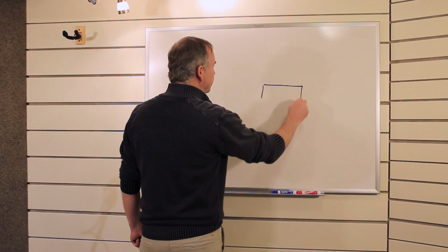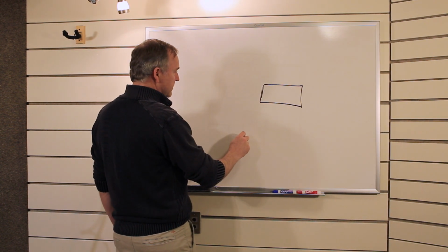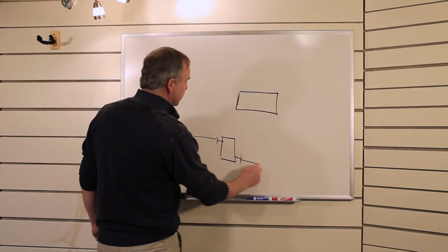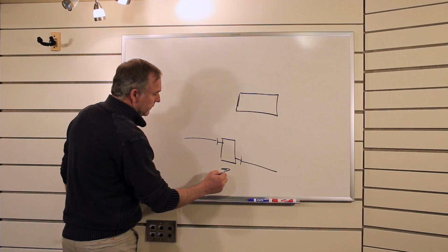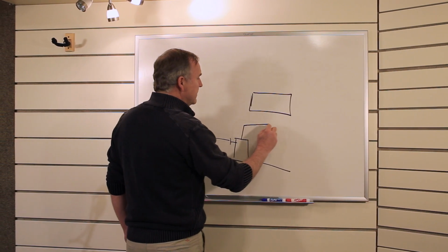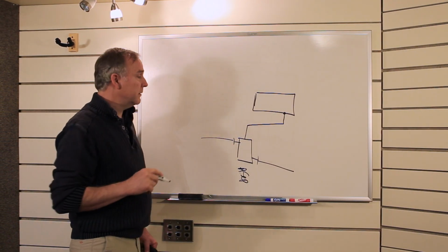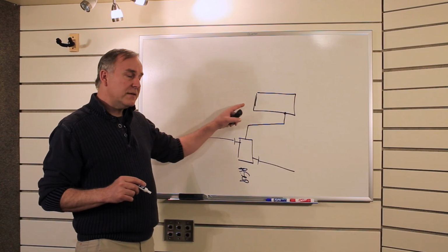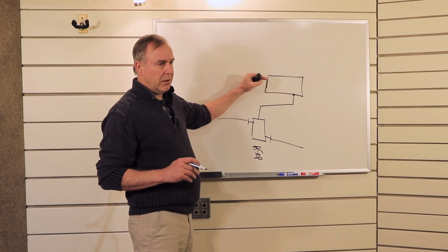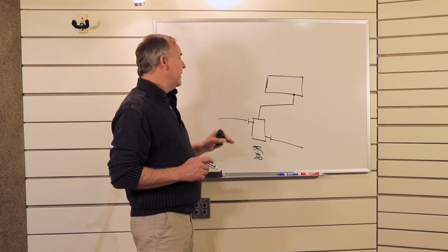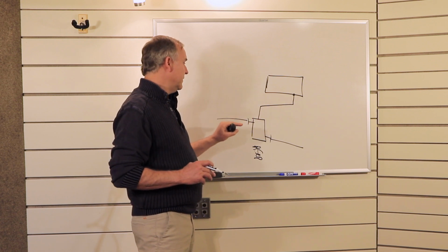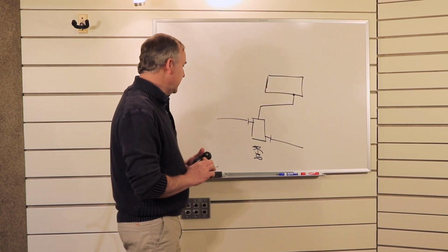If you have a plain steel tank, as represented by this little diagram here, and this is my hydronic system down here, this is my air separator here. The air separator always gets routed up and connected to a plain steel expansion tank. And the reason that we do that is that these plain steel tanks always have a tendency to want to get waterlogged. Essentially, they stop working. As a result of that, whatever air we separate out of the system, we try to divert that up. So the installation detail for them has us connecting them to the air separator.